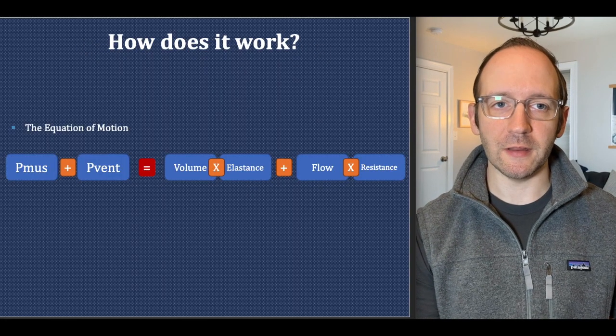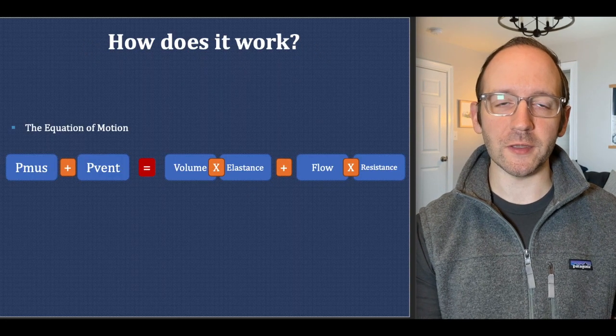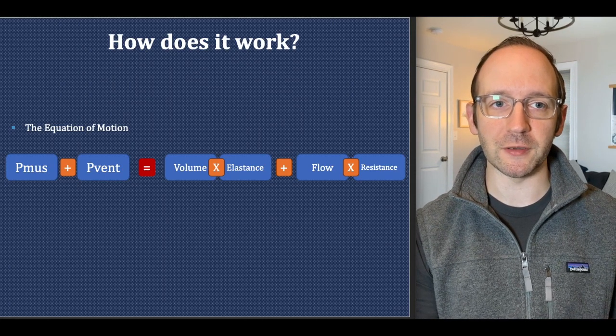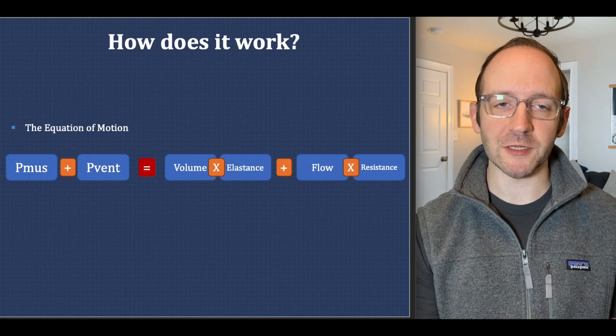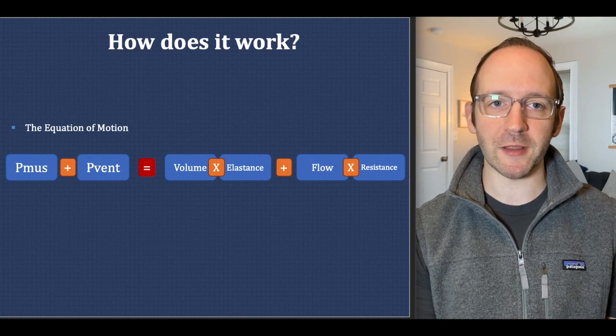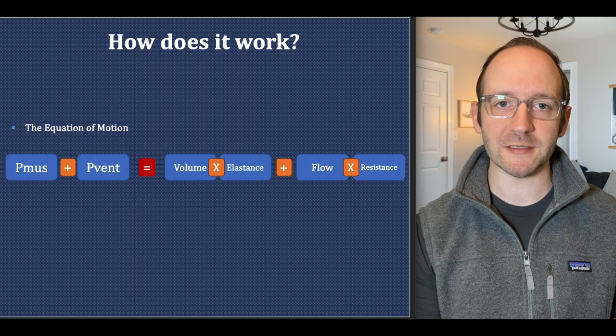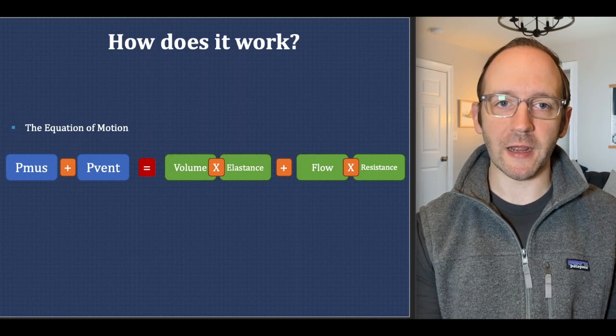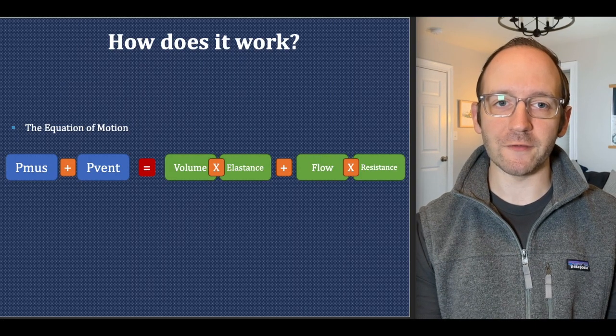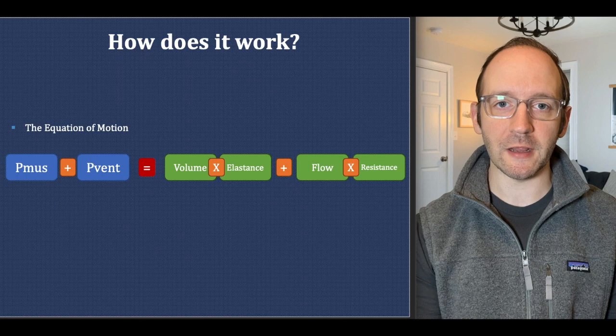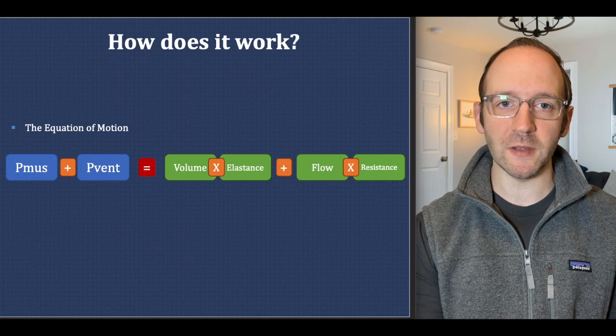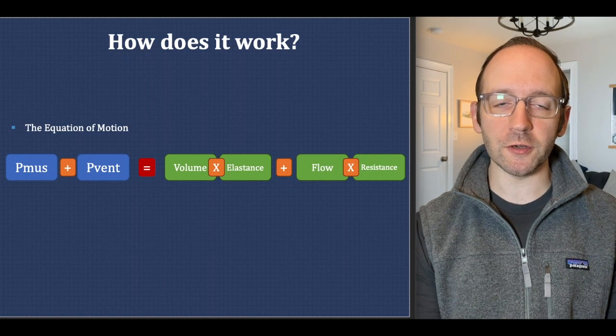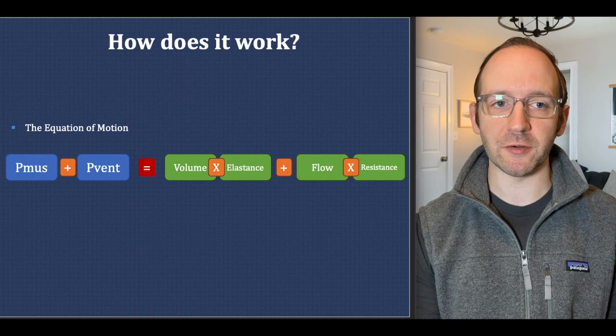So how does this mode actually work? It is completely reliant on the equation of motion — if you manage a ventilator, you need to know this equation. The pressure provided by the patient's muscles plus the pressure provided by the ventilator equals volume times elastance plus flow times resistance. PAV actually measures all the highlighted values: the tidal volume being breathed in, the flow, and then it calculates elastance and resistance to determine the total pressure needed to generate the breath.